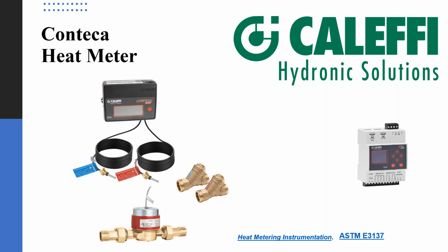And the Conteca system is a full heat meter. It controls, or it's able to see flows from a third of a GPM up to 1,000 GPM with the physical flow meter and the temperature taps. And then if you have multiple units of these, there's also a data logger, which everything networks into. So it makes your job easier. You don't have to go to the physical meter itself and record usage of each tenant. In this case, you would actually go back to the data logger and get that information given to you in a nice, neat, and tidy report.